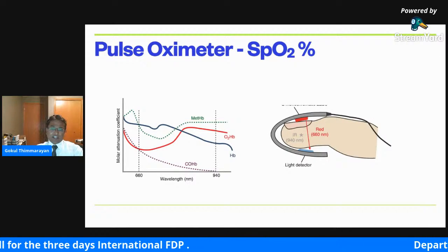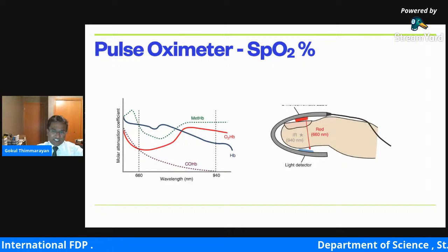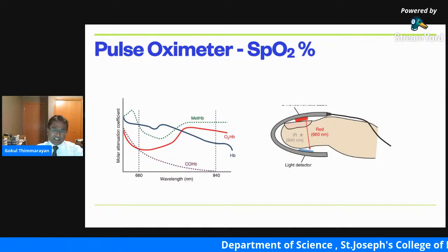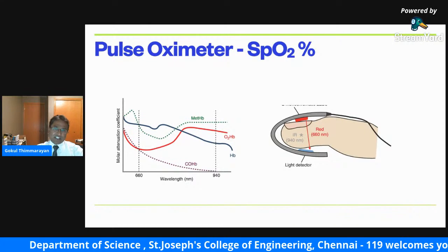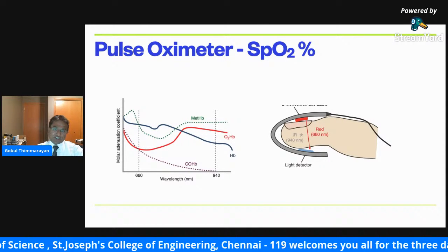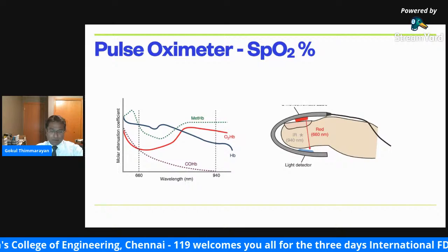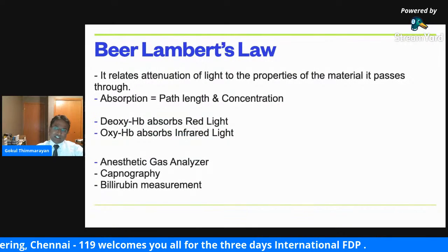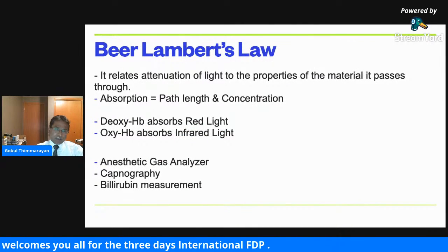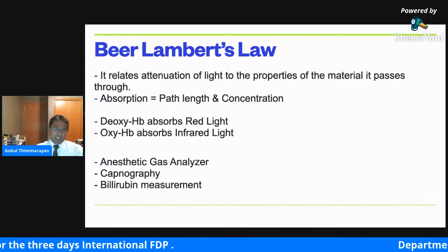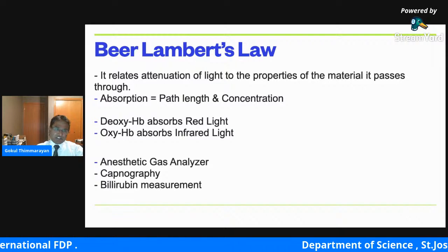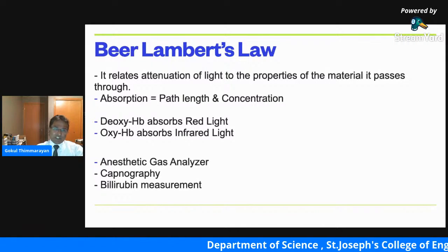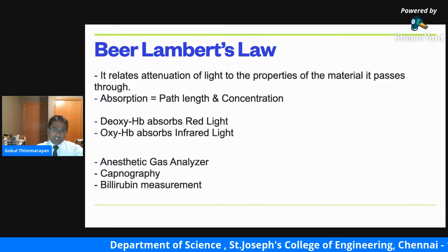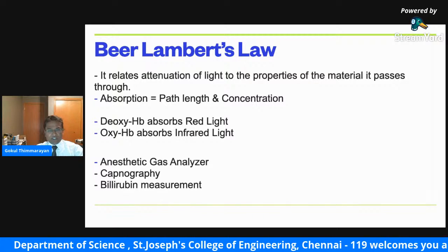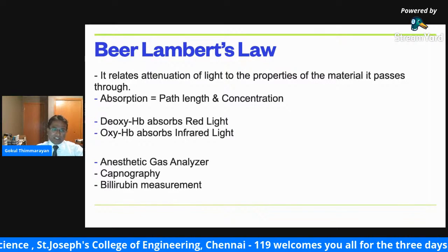The variation from the source to what is sensed in the detector helps in calculating the amount of oxygen in the blood, which is given as a percentage of oxygen saturation in the blood. And this is based on the physical principle, Beer-Lambert's law. The light gets attenuated as it passes through a material, and the amount of absorption depends on the concentration or the nature of the material that it passes through, the tissue and blood in this case, and the path length that it travels.